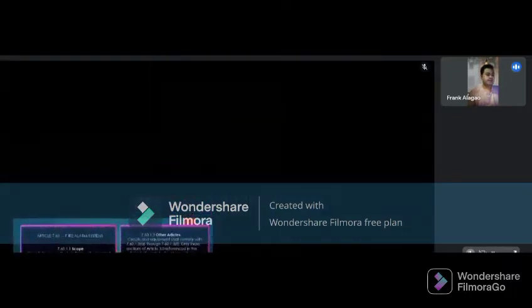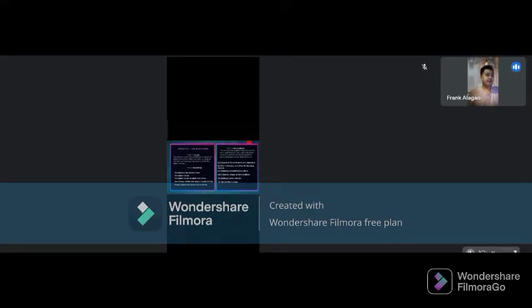So the portion of the wiring system between the load side of overcurrent device or the power limited supply and connected equipment of all circuits powered and controlled by the fire alarm system. So fire alarm circuits are classified as either non-power limited or power limited. Next is yung fire alarm circuit integrity cable or CI. So cable used in fire alarm system to ensure continued operation of critical circuits during a specified time under fire condition.